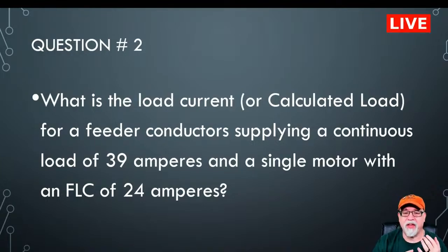Some people will say, well, wait a minute, I need to know the nameplate. No, you don't. Not to answer the question. In real life, you might need additional information. Obviously, if you go to overloads, you have to have a nameplate, because overloads don't use the FLC. They use the FLA, or the amps listed on the nameplate. But everything else, short circuit and ground fault protection, conductor sizing, feeders, all of those use the FLC values.